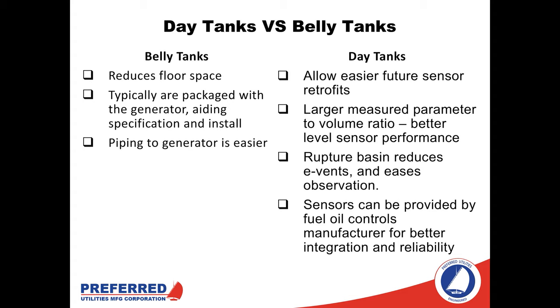With the belly tank, there's an advantage because it can typically be packaged with the generator — many cases see the sub-base floor as the belly tank or sub-base tank. It can be easy to specify and install, but it can pose a challenge when trying to integrate those level controls inside the tank with the existing control system. We generally recommend that sensors be provided by the fuel oil controls manufacturer for better integration, so that when startup comes and the two parts are integrated, the electronics talk to each other and signals are what they need to be.